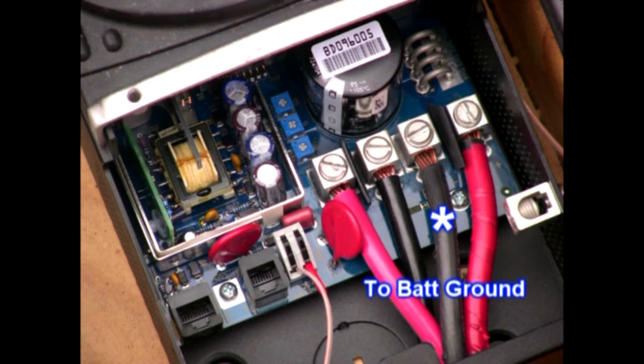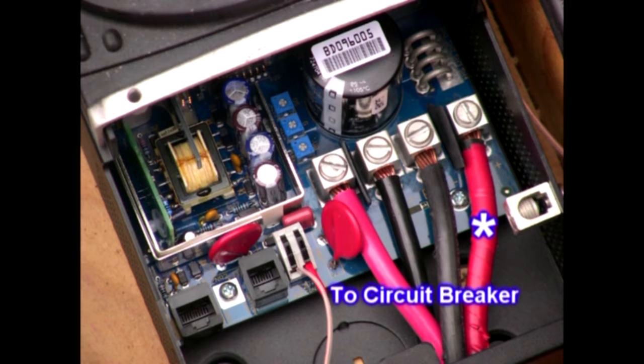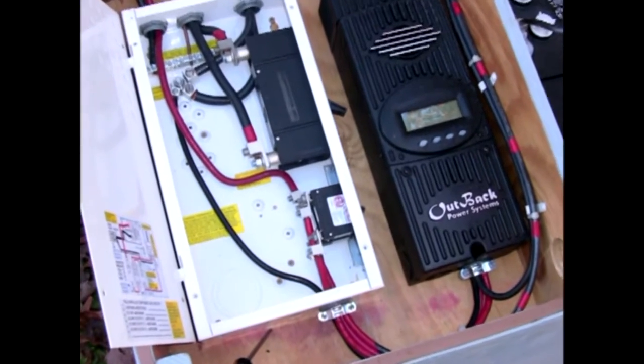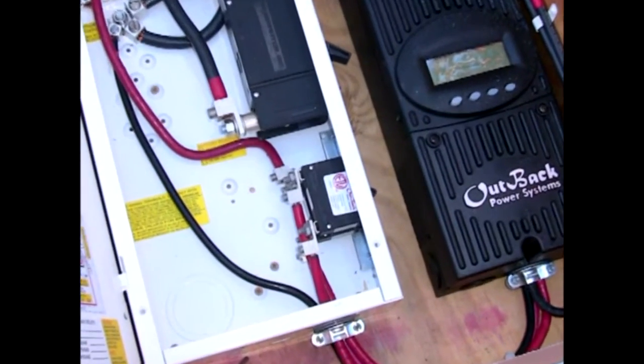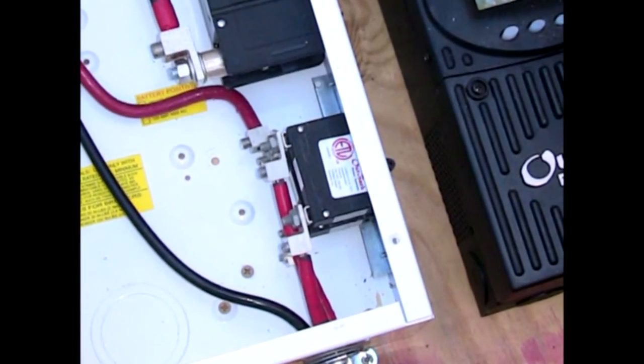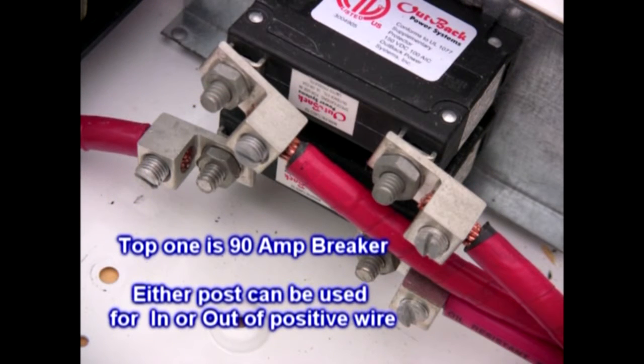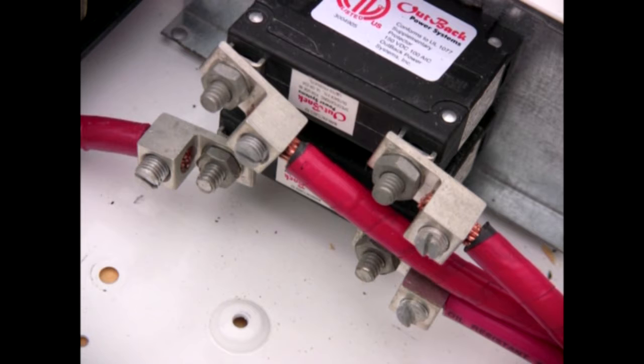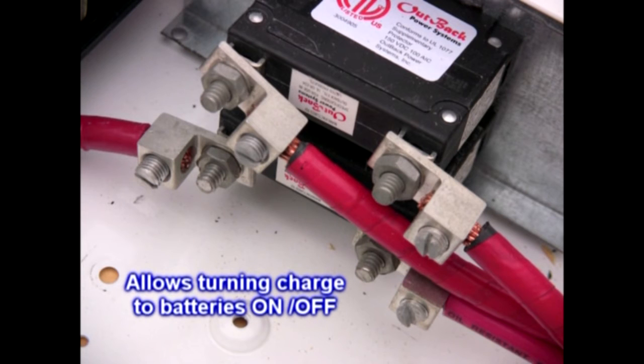One of those wires is going to go over to the batteries and directly connect to those. It's the ground. And the other one is going to come back into the circuit breaker box to go through another circuit breaker, in this case a 90 amp, because we know we have an 80 amp charge controller. It will never put out more than 80, so we're putting in 90 in there. 100 would be fine. You need a little bit of elbow room, and it's going to go back through a safety breaker that turns off the power between the batteries and the charge controller.